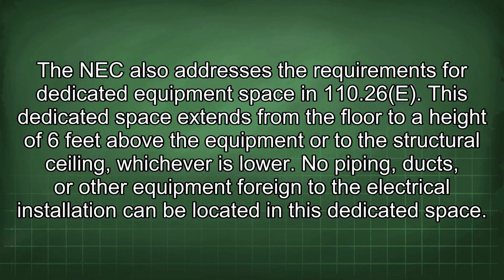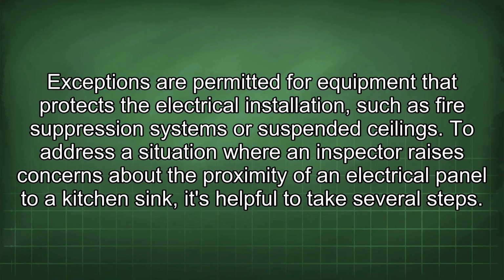This dedicated space extends from the floor to a height of 6 feet above the equipment or to the structural ceiling, whichever is lower. No piping, ducts, or other equipment foreign to the electrical installation can be located in this dedicated space. Exceptions are permitted for equipment that protects the electrical installation, such as fire suppression systems or suspended ceilings. To address a situation where an inspector raises concerns about the proximity of an electrical panel to a kitchen sink, it's helpful to take several steps.